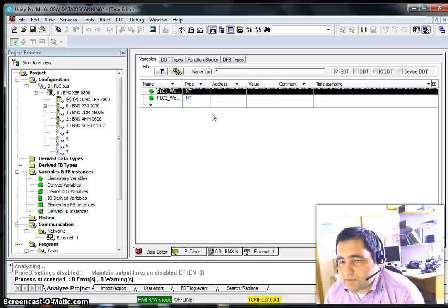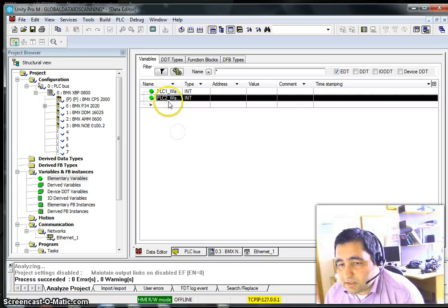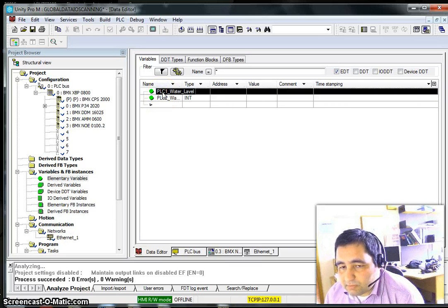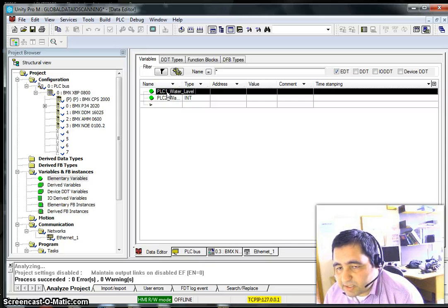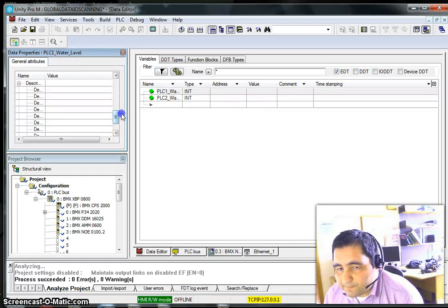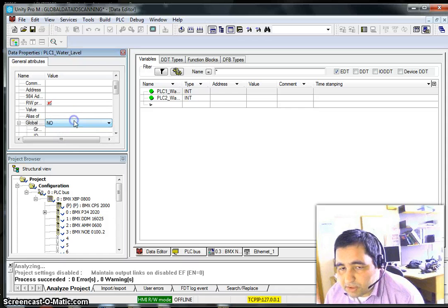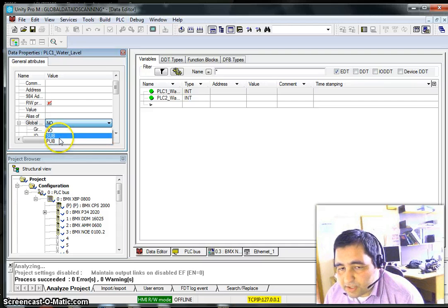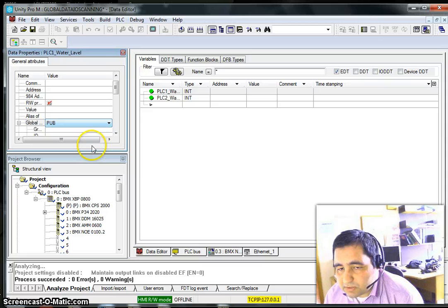Let's say the PLC we're using now is PLC1, and there's another PLC located somewhere else. If you want to use Global Data, you need to do some settings to make a variable global. To do that, right-click on the variable, go to Data Property, and change the Global setting. You can see that Global is currently 'No' — you can change it to either Publisher or Subscriber. This variable will be set as Publisher.